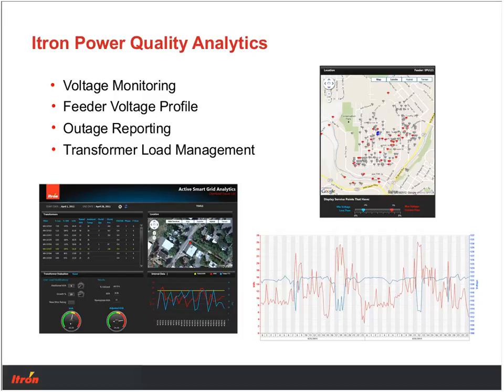Transformer load management, we may, if time allows, show a couple of shots of how we do that. It's basically aggregating to the transformer, running some fairly simple comparisons of your KVA to the nameplate rating, and some more sophisticated loss of life calculations based on IEEE standards that take into account weather, duration of loading, things like that.